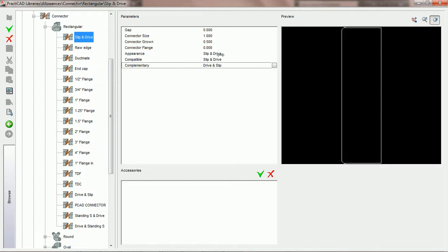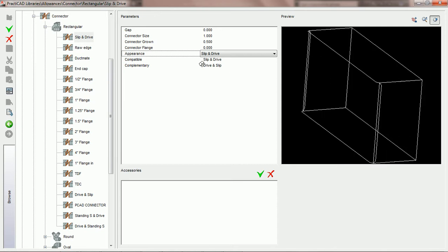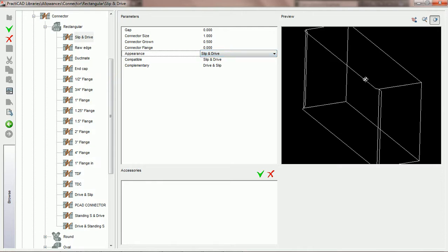we've chosen for it. First, we have the parameter for appearance. You'll notice that we've chosen the appearance slip and drive. Whenever we're representing an appearance, we're always reading the width first, then the depth. So if it says appearance slip and drive, it means on the width of the fitting is the slip and on the depth of the fitting is the drive. You can see here that on the width of this fitting, as we move over it with our cursor, you can see a preview of a slip. And on the depth of the fitting, you can see a preview of the drive. So it's width by depth, slip and drive.